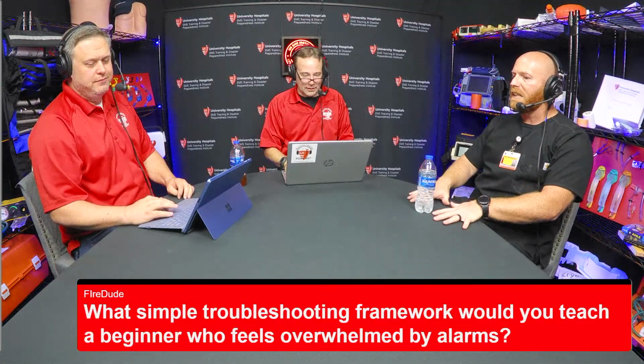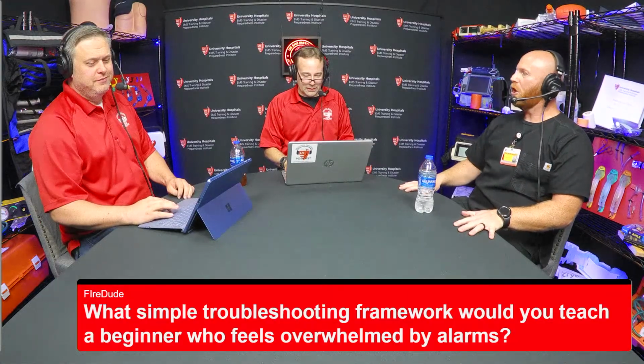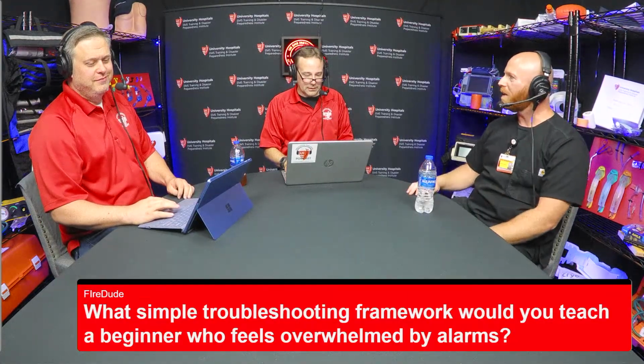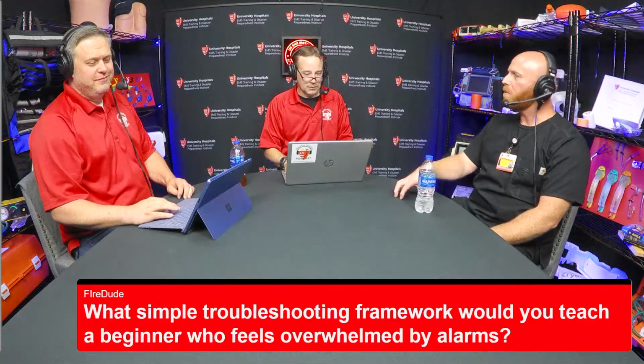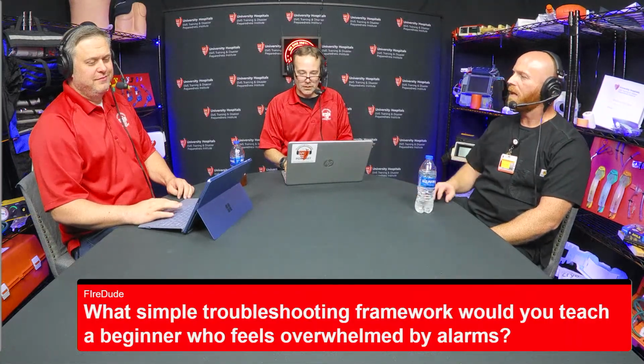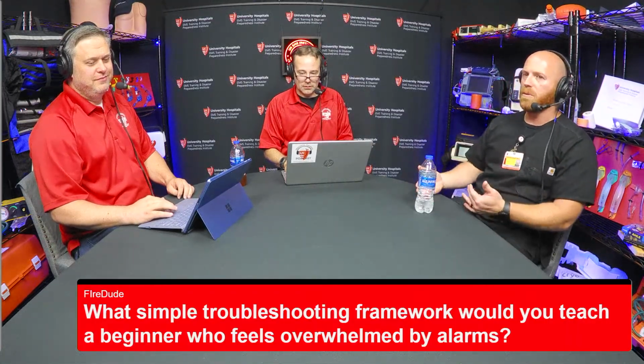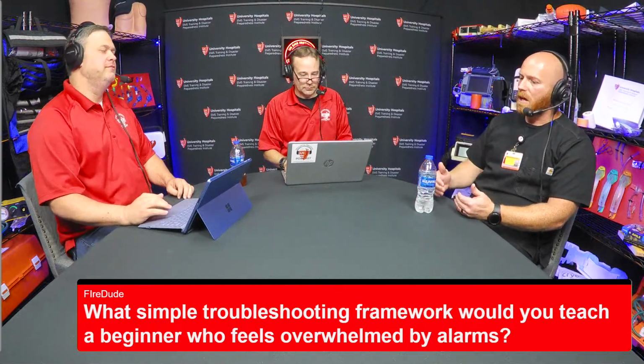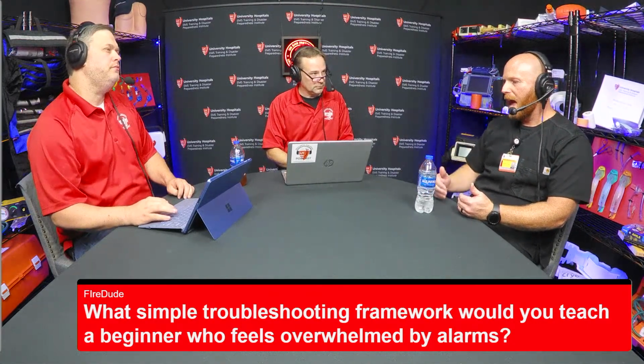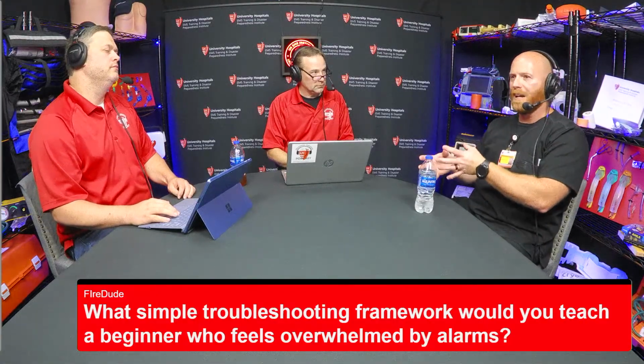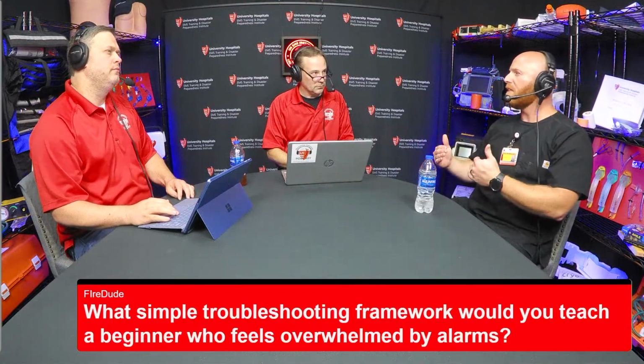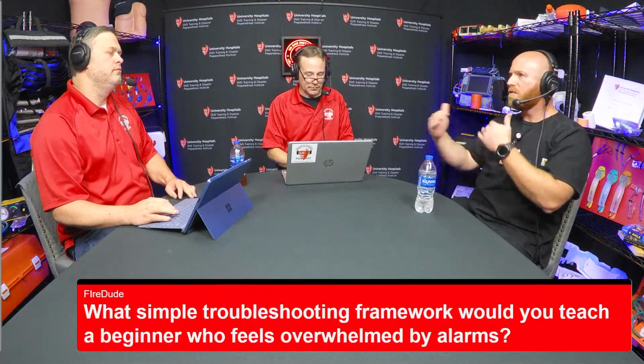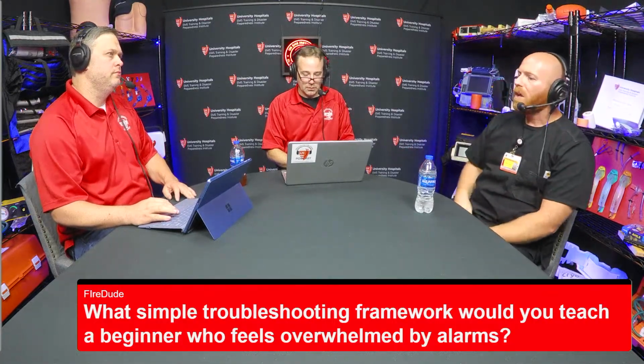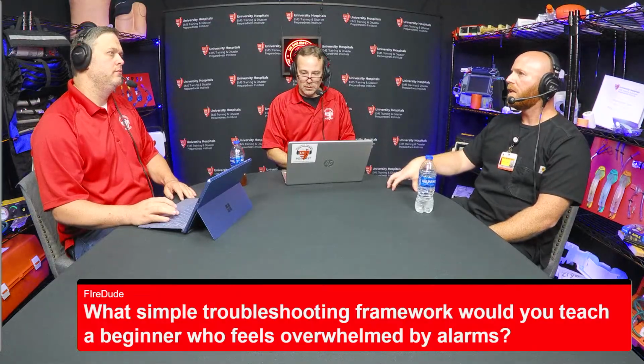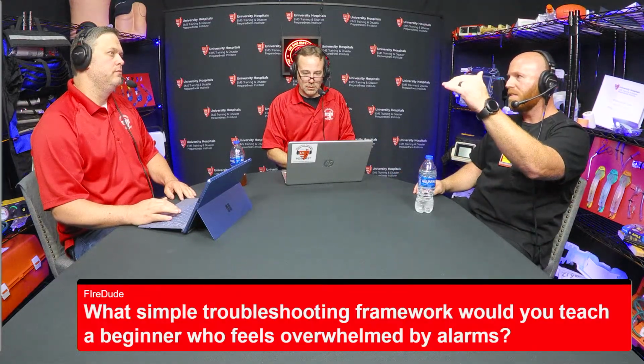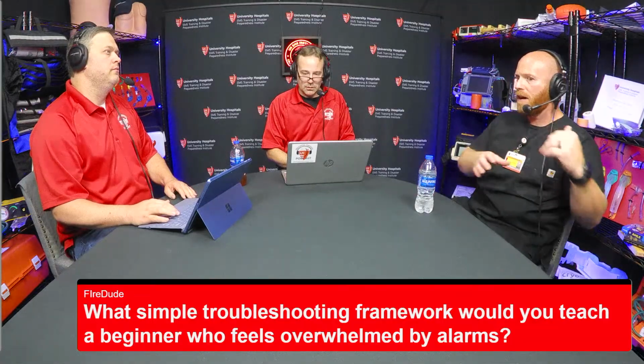There's obviously a lot of things that can cause alarms, and we don't have all the time to talk about that. But making sure they're set appropriately is the number one thing. And our protocol in hospital is that we set our alarms double above or half below what the patient's actually doing. And that's just a baseline. We can vary from that. We should vary from that to tune it per patient. But as long as they're set appropriately, then we need to find out what the alarm is, and then figure out how to fix it.